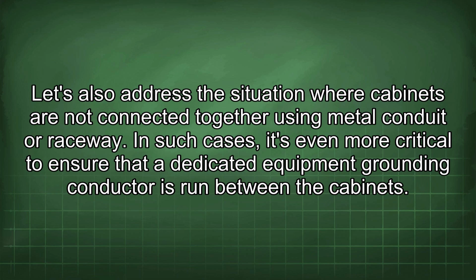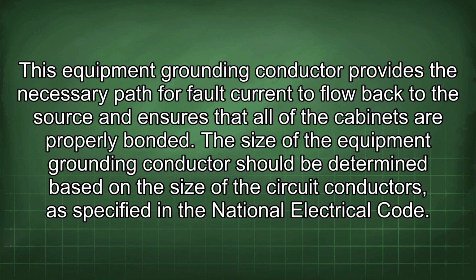In such cases, it's even more critical to ensure that a dedicated equipment grounding conductor is run between the cabinets. This equipment grounding conductor provides the necessary path for fault current to flow back to the source and ensures that all of the cabinets are properly bonded. The size of the equipment grounding conductor should be determined based on the size of the circuit conductors, as specified in the National Electrical Code.